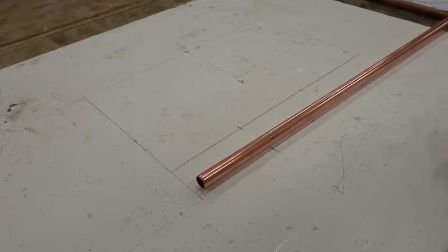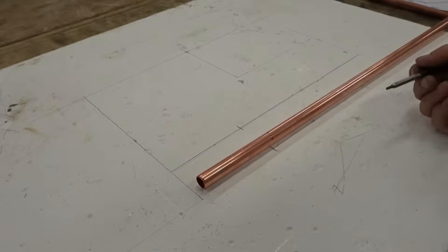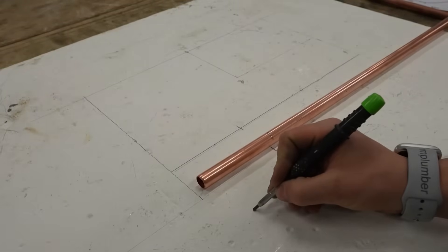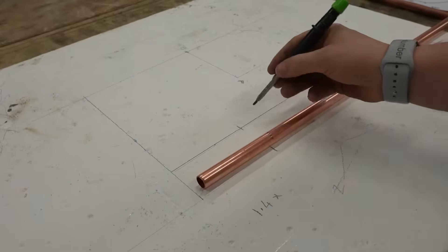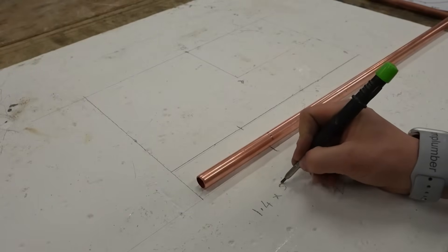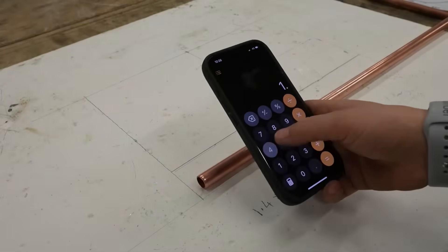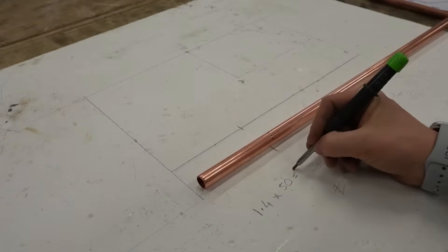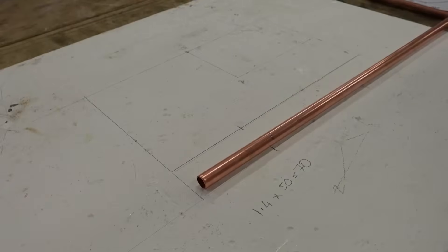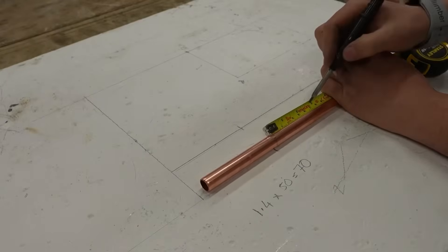I'm going to show you a little trick with these Monument pipe benders that allows you to get a 45 degree bend perfect every time. It's a simple formula: 1.4 times your set measurement. We need 50mm, so 1.4 times 50 equals 70mm. Now we have that measurement, go ahead and mark 70mm on our pipe.